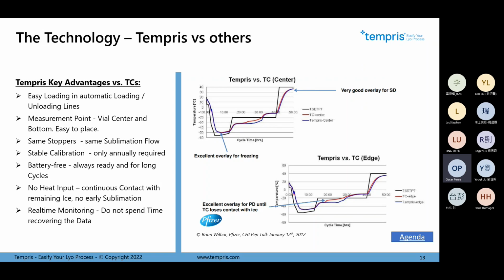It doesn't happen with other technologies. They have maybe some resistance, a battery, and a cable going from the battery to the measurement point, and this cable is very near the upper shelf, for example. So the upper shelf radiates some temperature to the cable, which goes inside, even when it's insulated, all the way to the point of measurement.